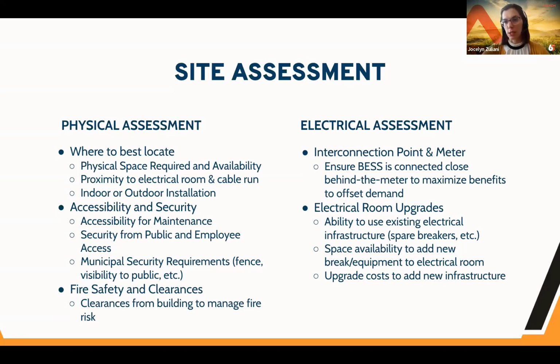With brownfield locations and industrial facilities, determining where to locate the battery often requires some time. It requires coming to the site and looking at where there's physical space available. Should it be indoors or an outdoor installation? Generally the preference is outdoor, but that's not always possible depending on available land area and proximity to the electrical room. Ideally we want to be close to the electrical room and interconnection point to minimize losses on the cable and costs.